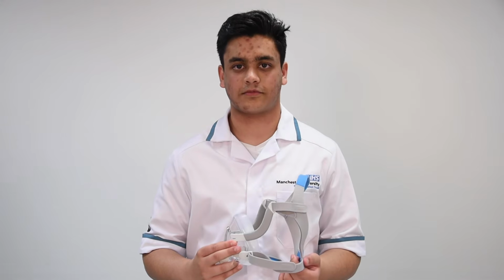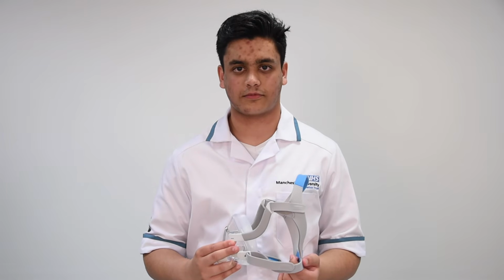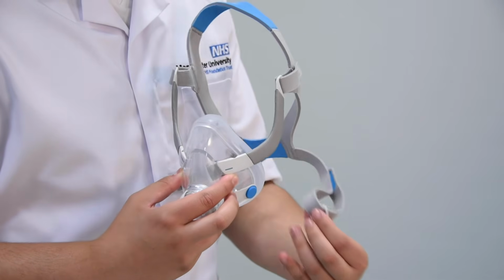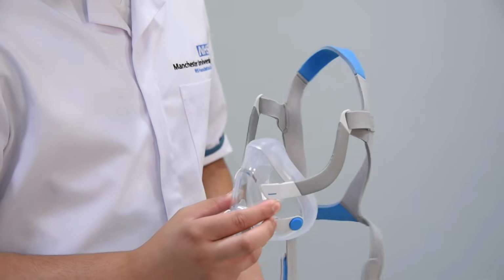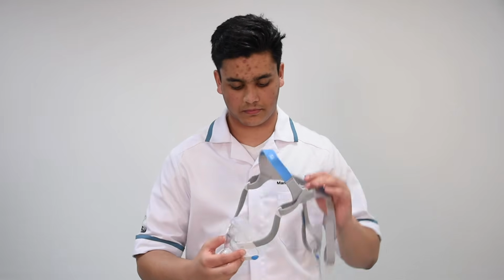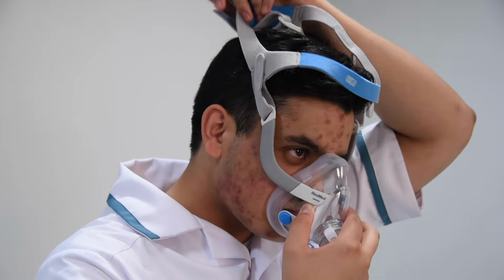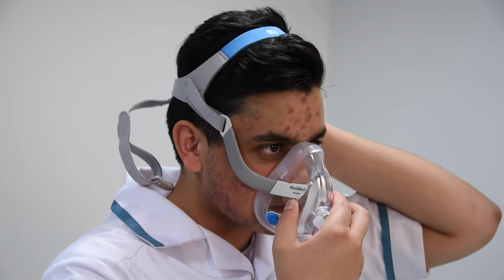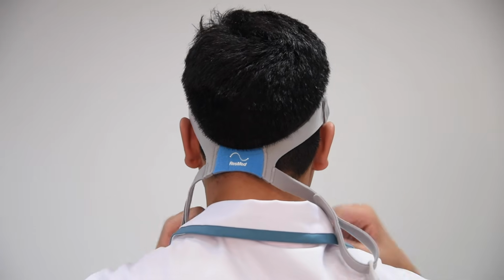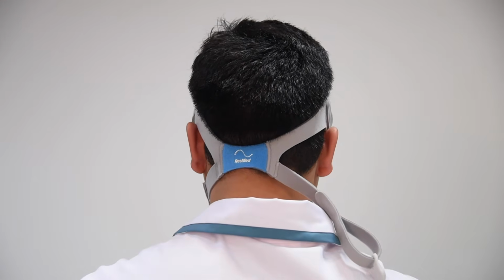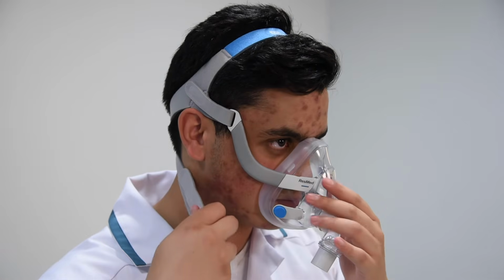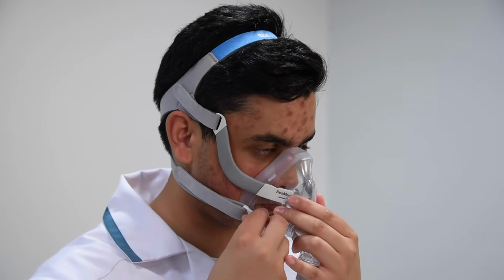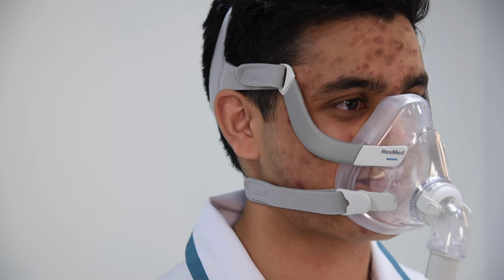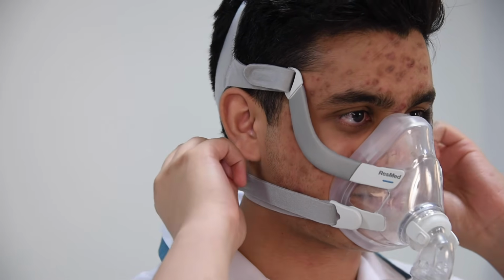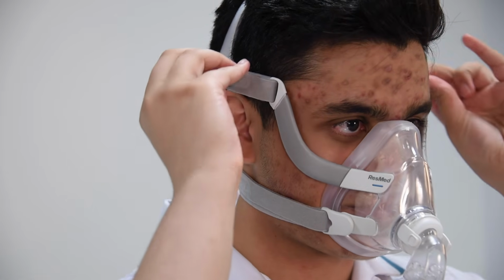As you are new to the CPAP machine, it is easy to fit your mask in a mirror or with the help of a relative or friend. Remove the 2 magnetic clips attached to the frame. Place the mask cushion on the bridge of the nose and below the bottom lip but above the chin. Bring the headgear over the back of your head. And attach the magnetic clips to the frame on each side. To tighten the mask, use the Velcro strips on each side to ensure the mask is fitted firmly to the face.